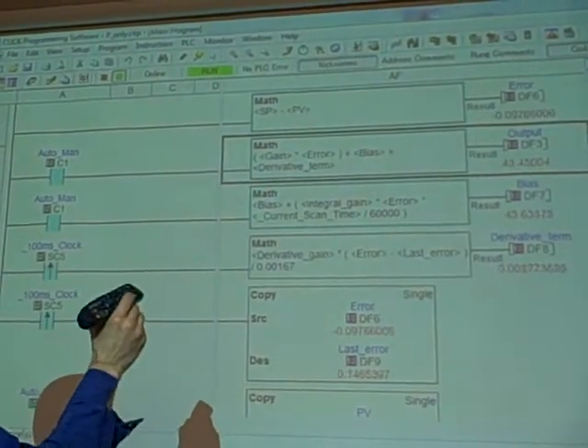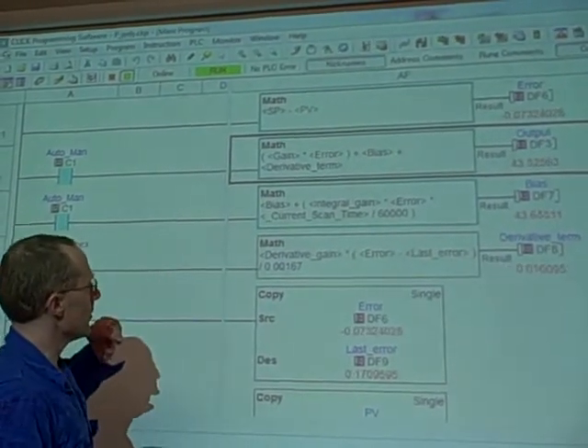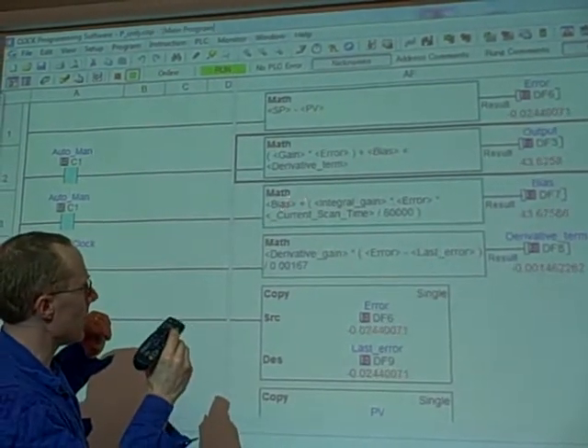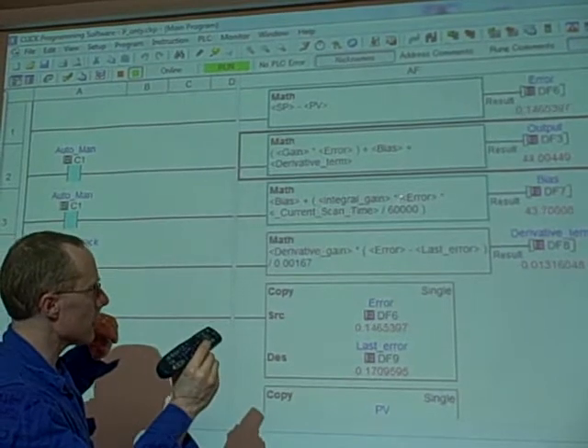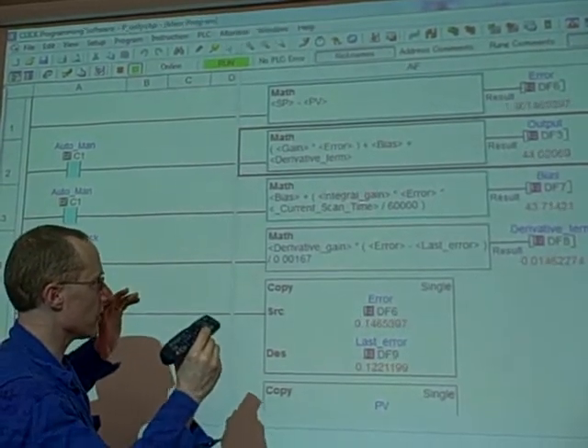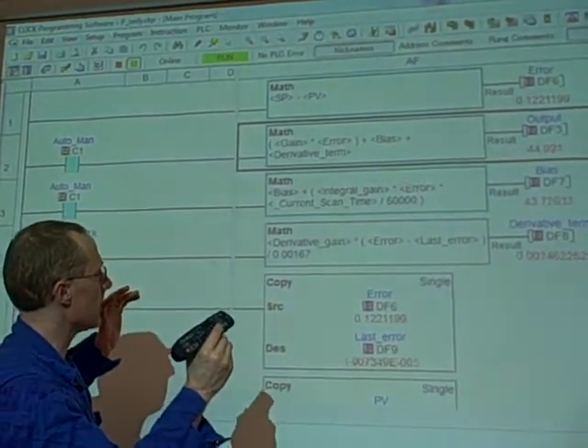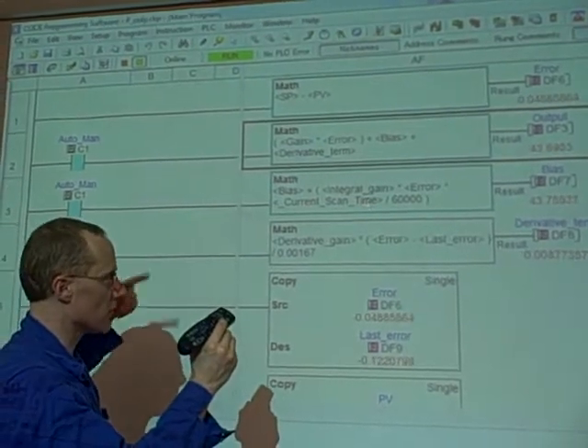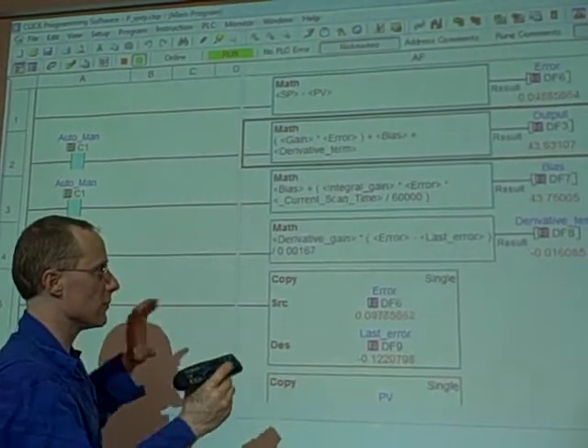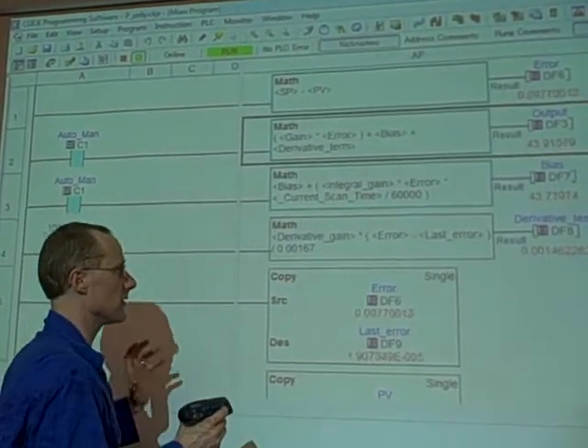Here, in this box, we're calculating integral. We're taking whatever bias value is, and we're adding to that the integration, the product of the integral gain times the amount of error we have times the current scan time, divided by 60,000 to put in units of repeats per minute.